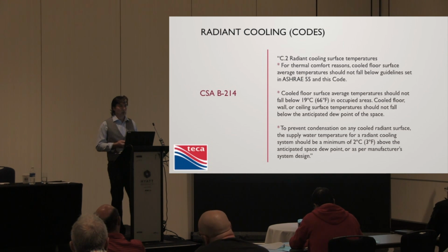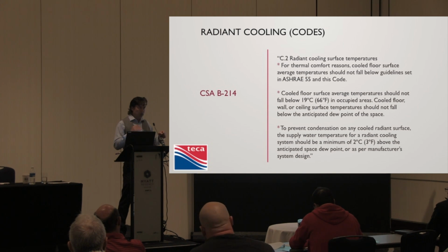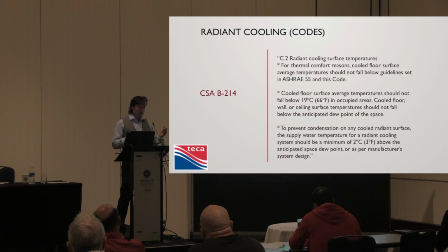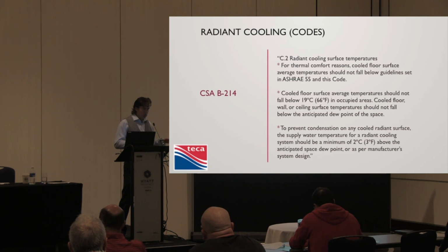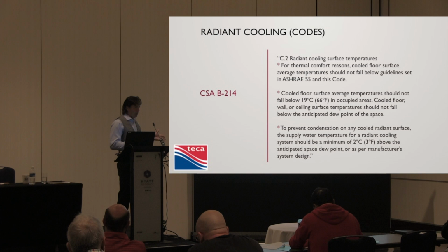Well, number one, we're going to have to know where the dew point is. So we're going to have to sense temperature and humidity in the room and understand where our dew point is going to be and modulate our chilled water accordingly. It's getting to be a lot of work here, control-wise. For your house, with your hardwood floor, and your latent load, is it great for a home in certain applications? But the amount to set it up and be safe with it and maintain this, and you'll see this all over the place, 3 degrees above the dew point with the circulated water temperature, that changes, just as humidity changes in the room. So it's a complex thing to do.